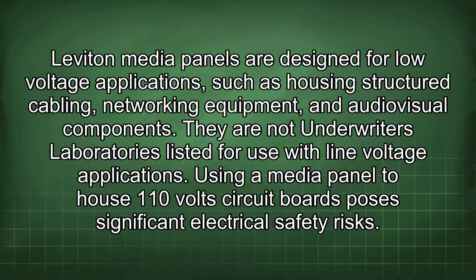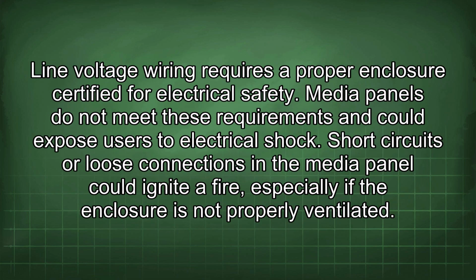Leviton media panels are designed for low-voltage applications such as housing structured cabling, networking equipment, and audiovisual components. They are not listed by UL (Underwriters Laboratories) for use with line voltage applications. Using a media panel to house 110-volt circuit boards poses significant electrical safety risks. Line voltage wiring requires a proper enclosure certified for electrical safety. Media panels do not meet these requirements and could expose users to electrical shock.